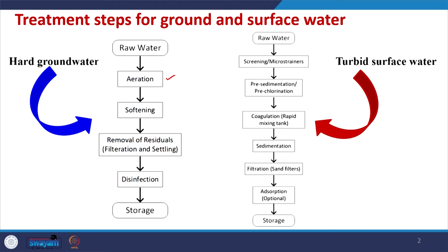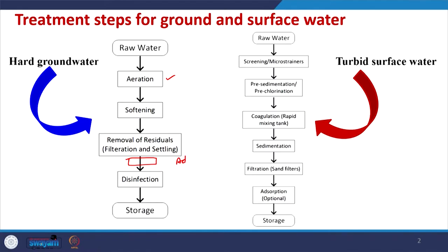For softening, we do the softening process so that hard water is softened before use. Some other types of impurities or residuals may be present in the ground water, and those residuals have to be filtered and settled out. If arsenic is present in the ground water, arsenic also has to be removed, so we may include an adsorption step. Since we are going to use the water for drinking, we have to perform disinfection to remove the maximum amount of pathogens before storing and distributing it.